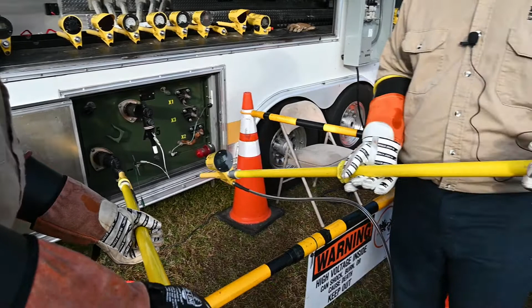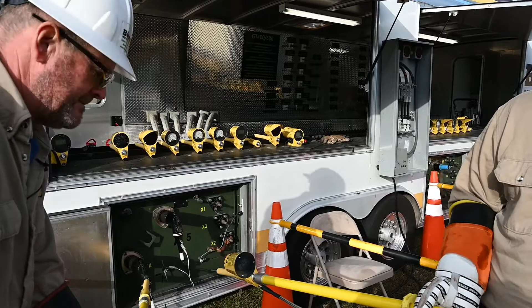So here we've got right at 340 volts, and here we've got right at 260 volts, so about 80 volts difference. When we go phase to phase and we're out of phase, we'll see that 1.72 multiplier, about 500-600 volts. If we're in phase, we'll see the difference of about 80 volts. So we see close to 75 volts, 74 volts. Not quite zero, but definitely not that 1.72 multiplier we would see if we were out of phase. So we know these two elbows are the same phase. We're just confirming the phasing there.